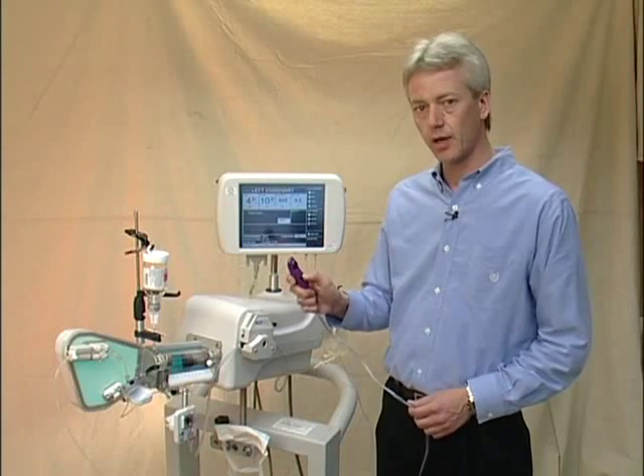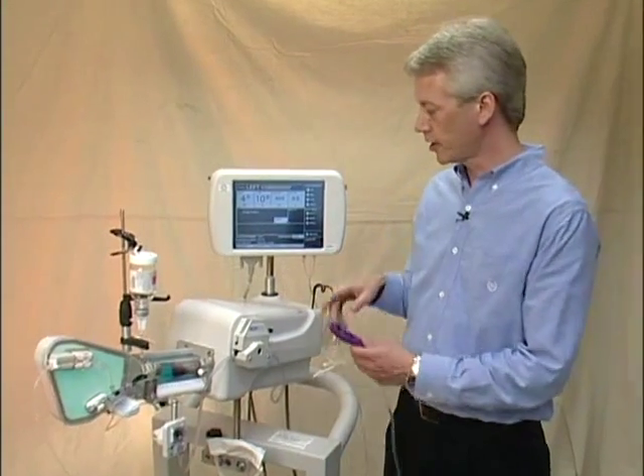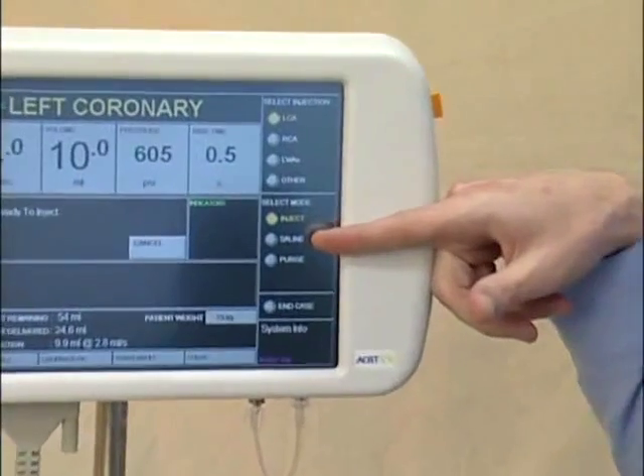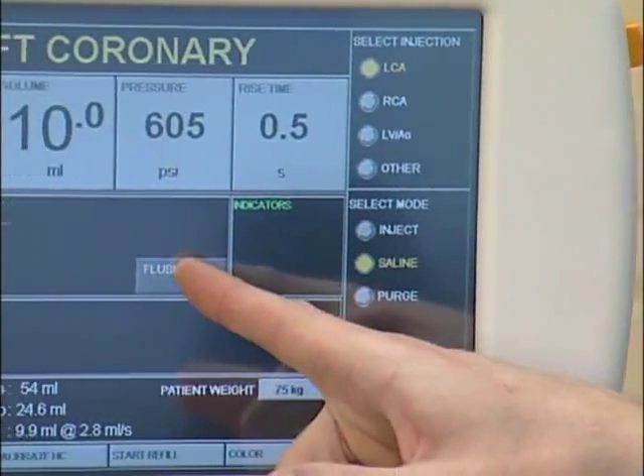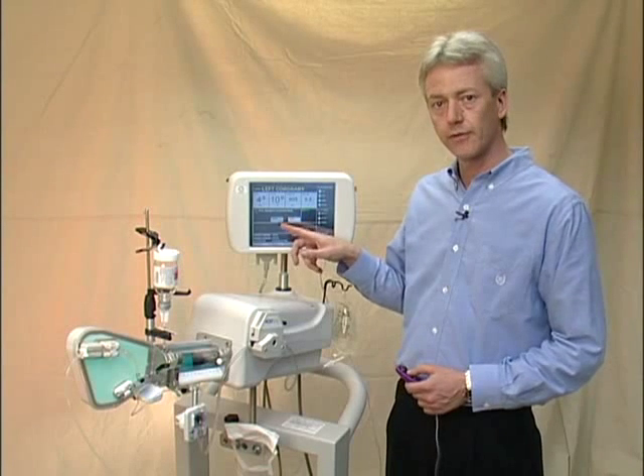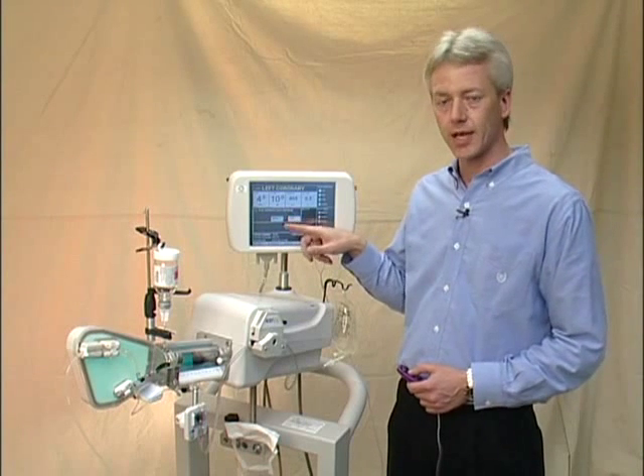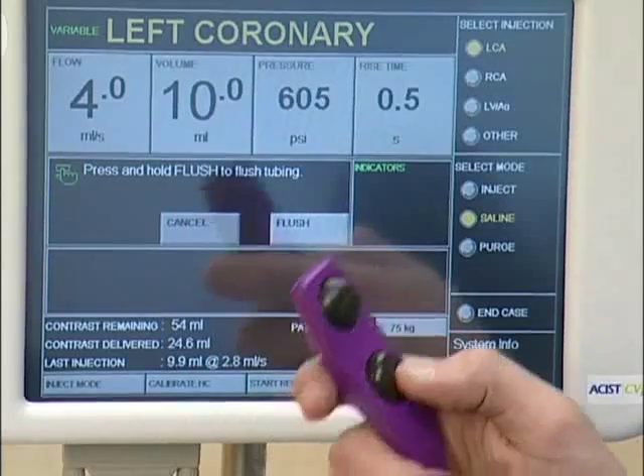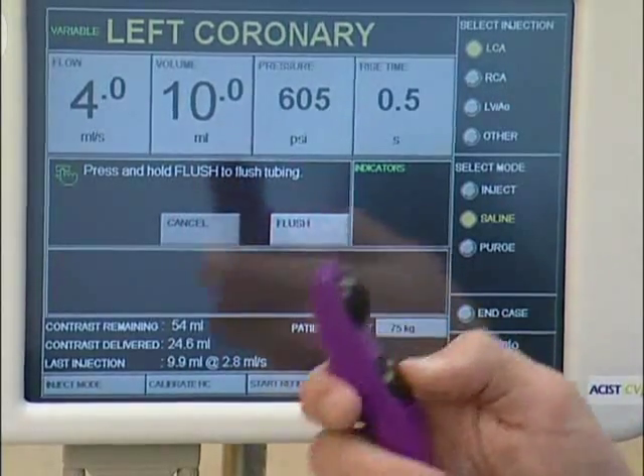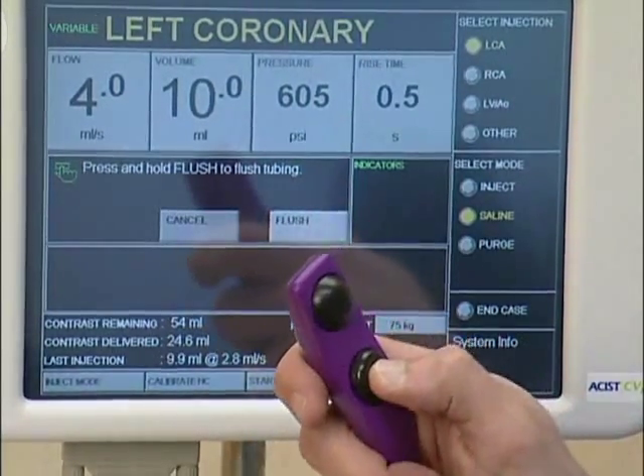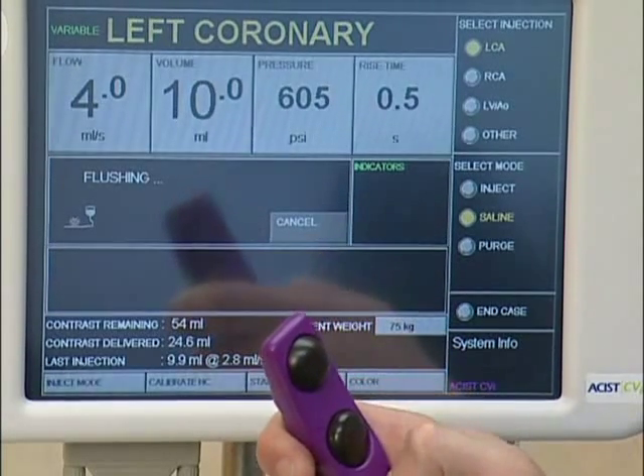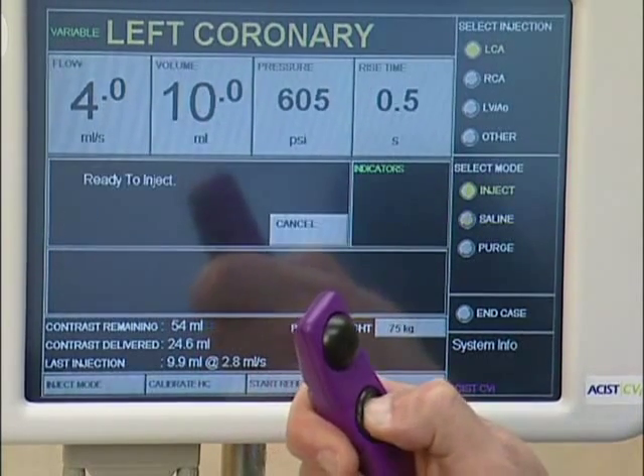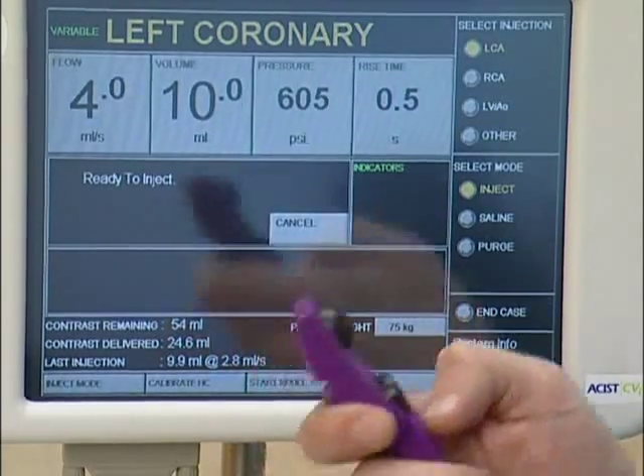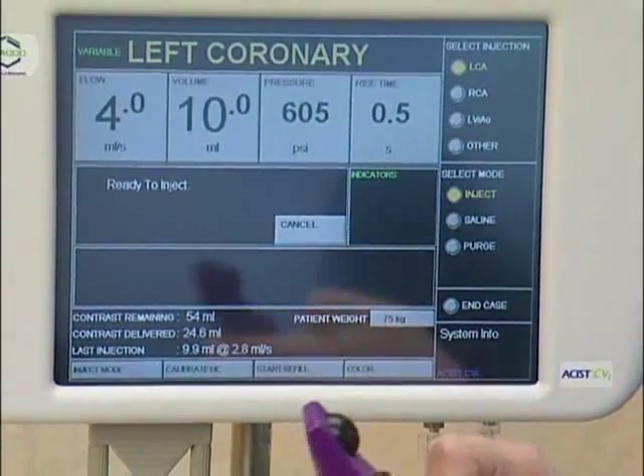You can either use the saline button on the hand controller, or that function is also on the control panel as well. Pressing it from the control panel is a touch and hold function. The saline flush will be delivered for as long as you touch the button, with a 10-second timeout limit. The function from the hand controller works like an on-off switch. So once you press the saline button once, that will start the saline. Press it once more and the saline flush will stop. That also has a 10-second timeout limit as well.